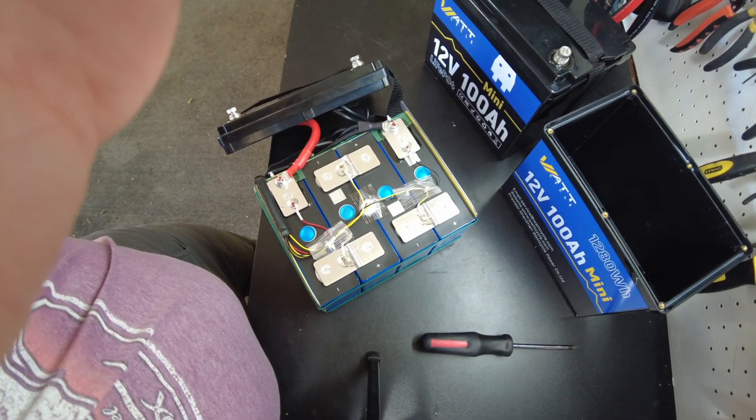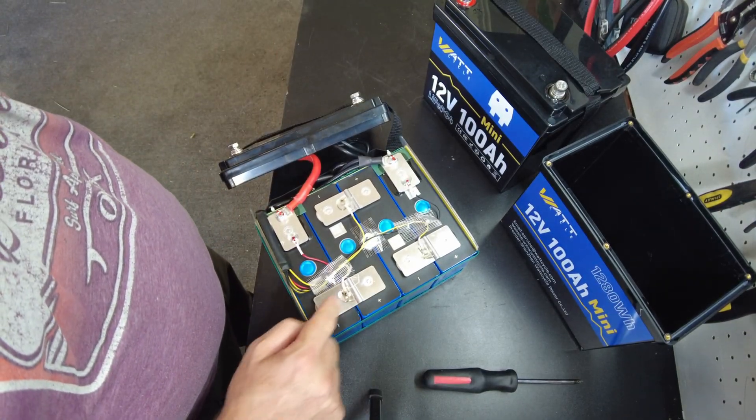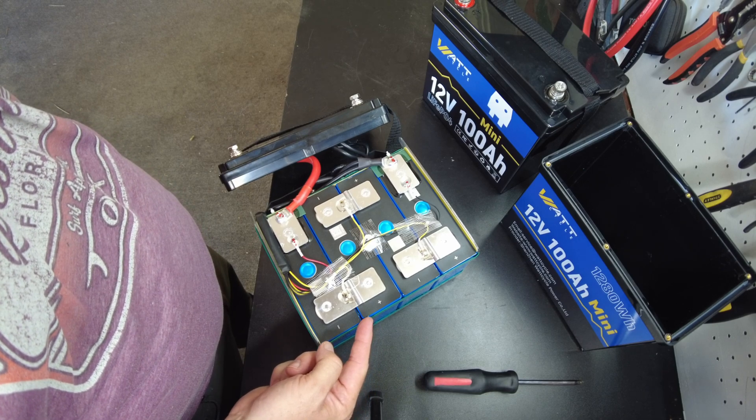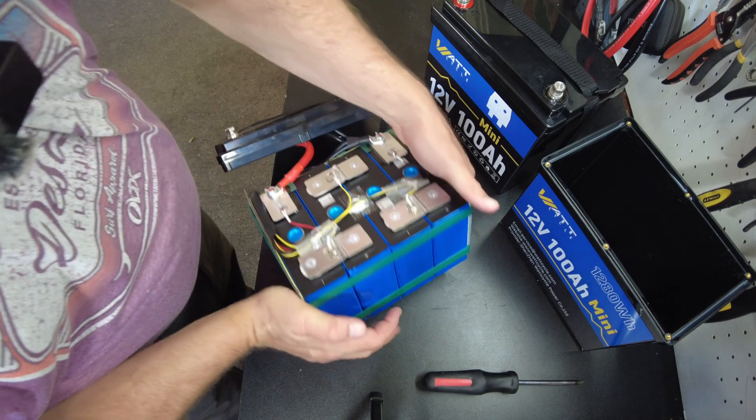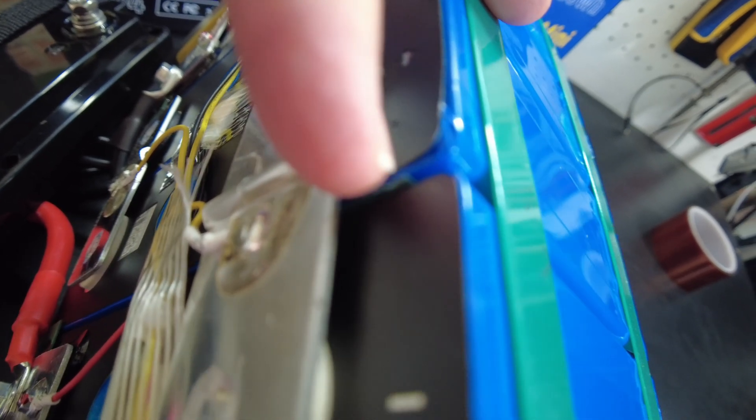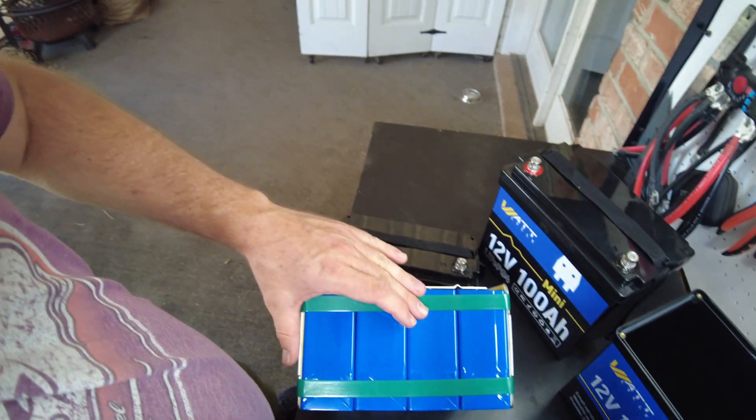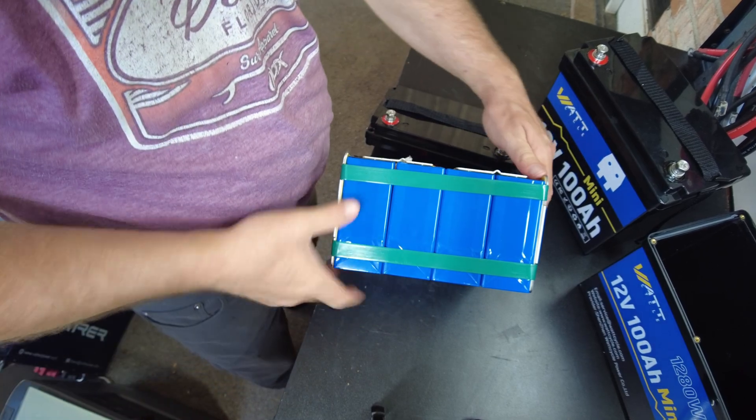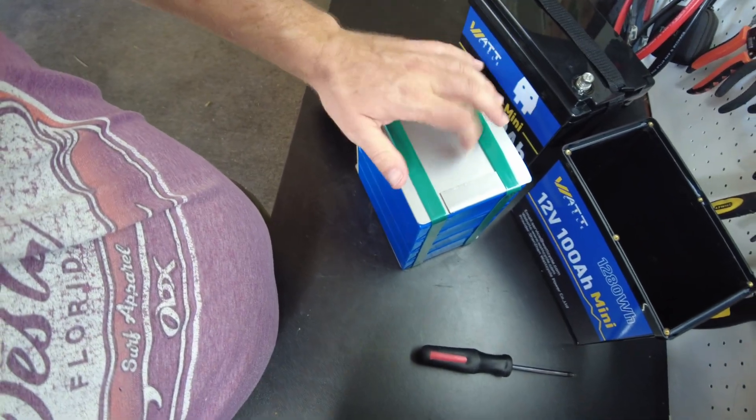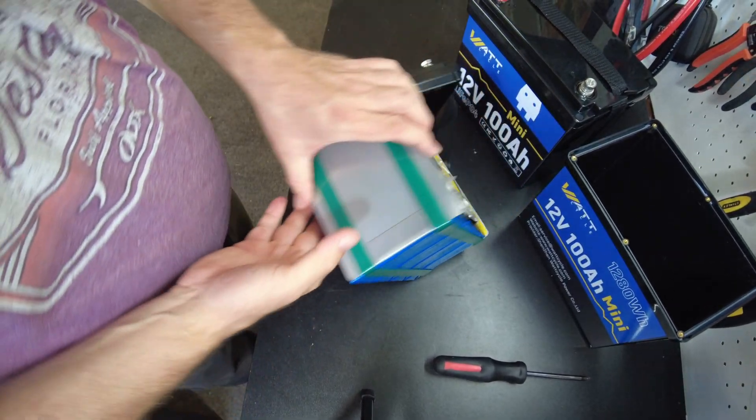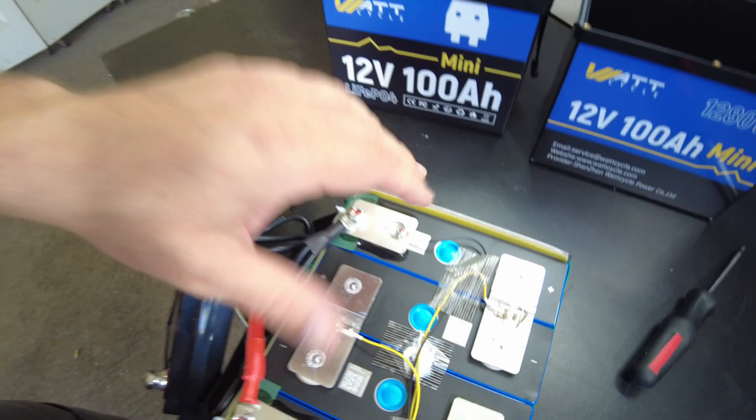So let's see what we got. So there's the top of the cells. We have aluminum laser welded bus bars. They do have a relief hump in them. There is in fact insulation material between the cells. It's hard to see, but there's the edge of it right there. I don't know if you can see that very well. There is definitely something between there, so they are isolated from one another, which is good. The cells are held together with this banding and there's these metal plates on the sides. And between the metal plates and the cells, obviously there's this fiber board. That's good.